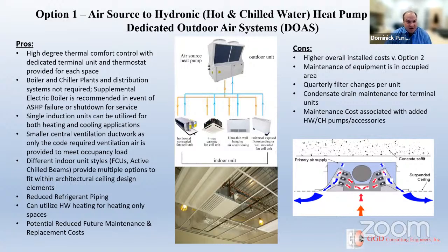We've identified the pros and cons, and the pros on these and why we're comfortable with all these options. They will provide a high degree of thermal comfort. With this option, you don't need a separate boiler and chiller plant. You've got an air source heat pump that produces hot water and chilled water. And again, the terminal units can provide heating or cooling. And it reduces refrigerant piping by using hot water and chilled water systems. So often people don't want to run refrigerant piping throughout the building.